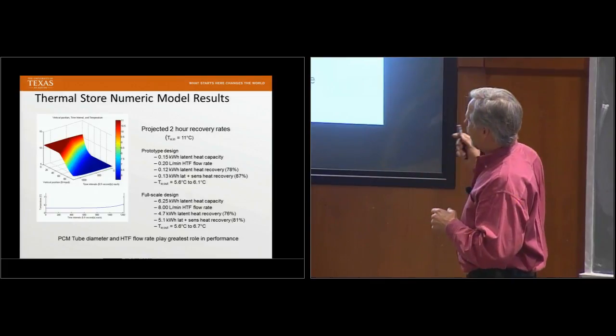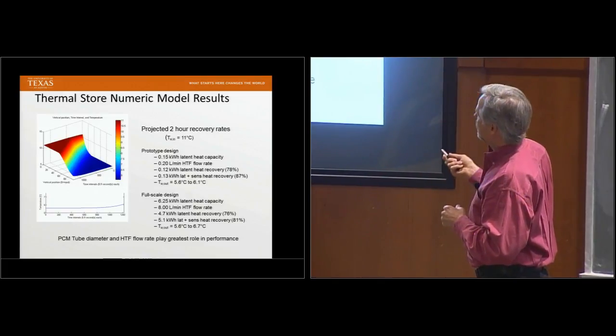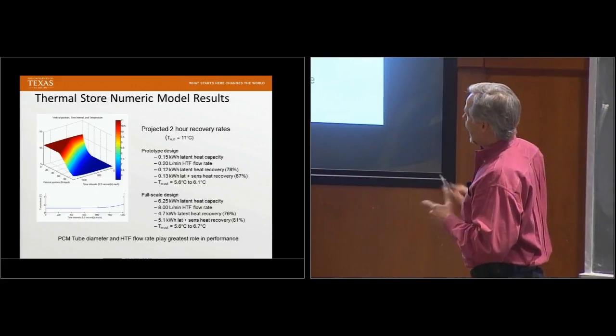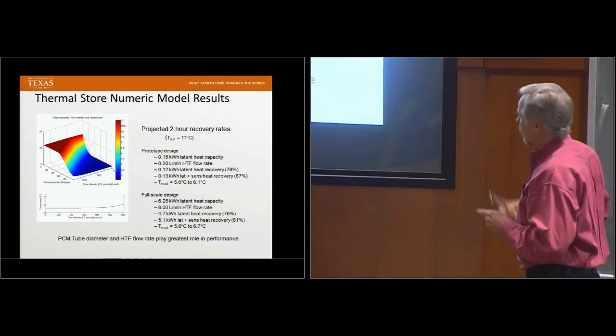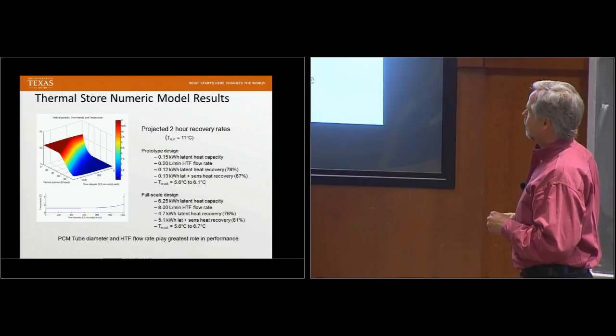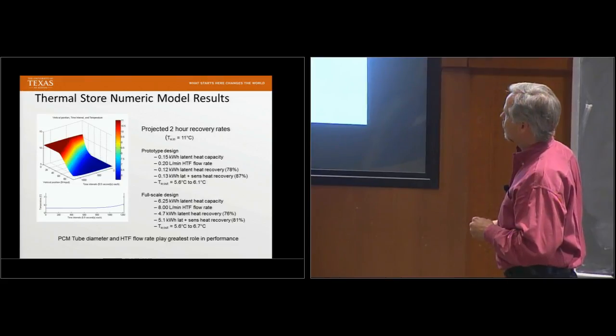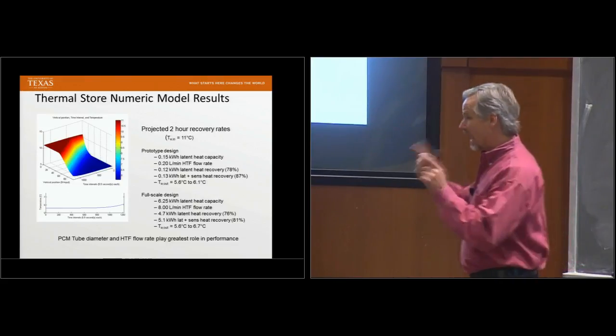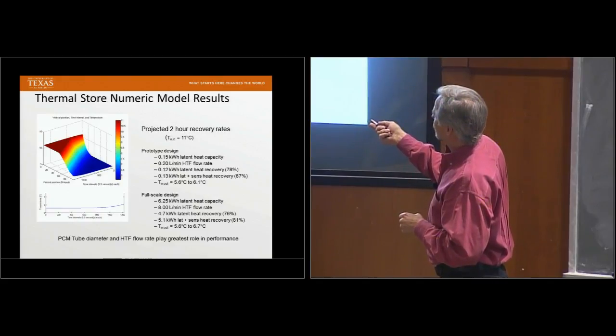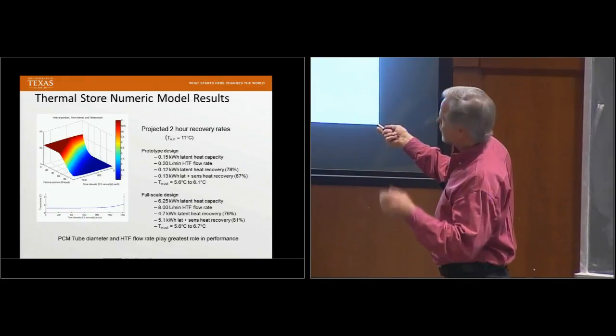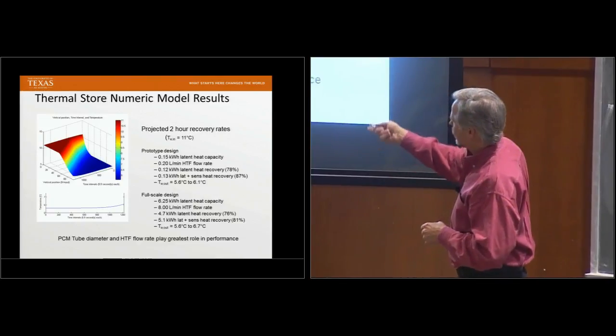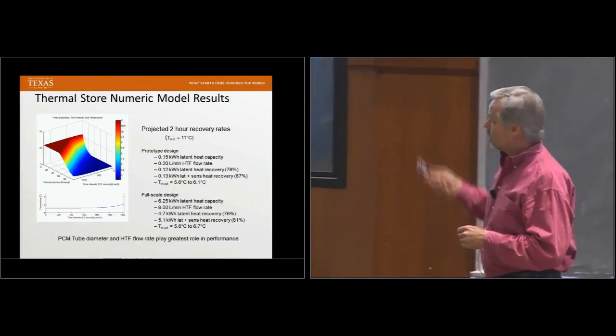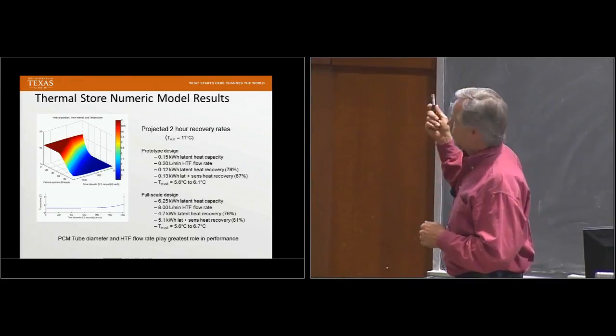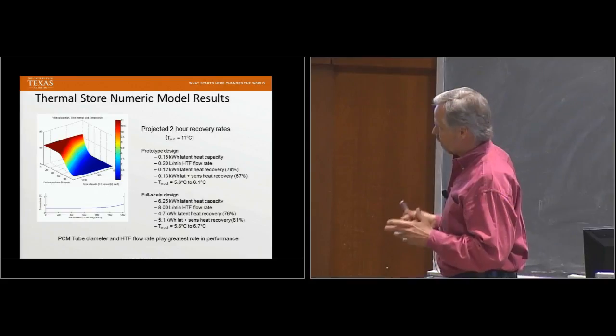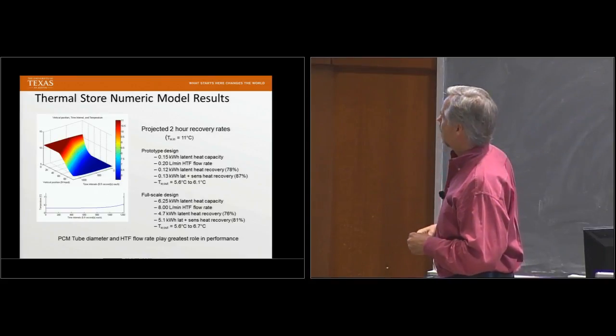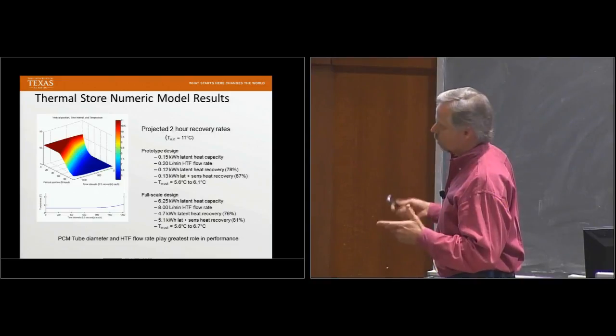What the model's telling us is that for the prototype design, we get 78% of the latent heat recovery energy out of that store in just a 2-hour period, and we get it out at a useful temperature. The temperature range varies from 5.6 degrees C, which is the freezing point of the PCM, to 6.1 degrees C as it climbs as we consume the thermal store. So we're getting exactly the results we hope to get. And this tells us that it is very suitable for air conditioning applications, that we can use this to offset some of the electricity normally used for air conditioning.